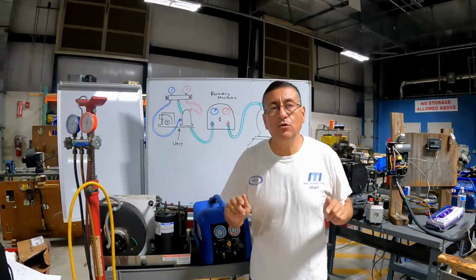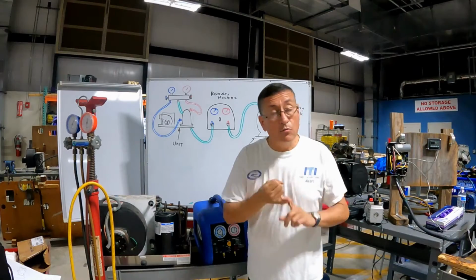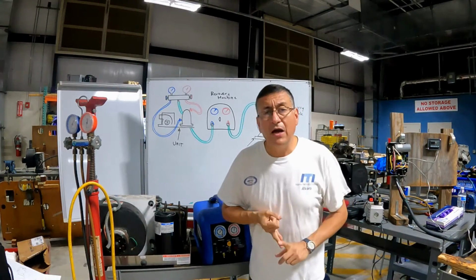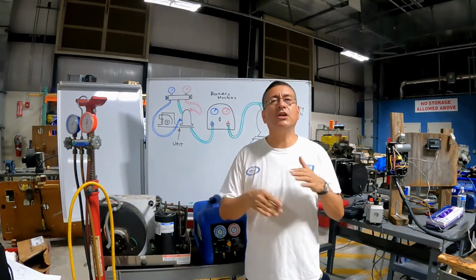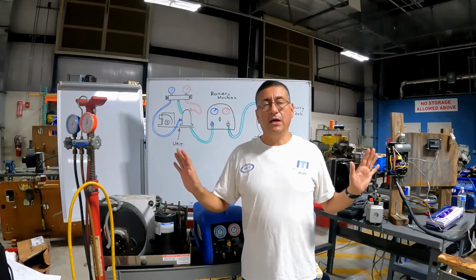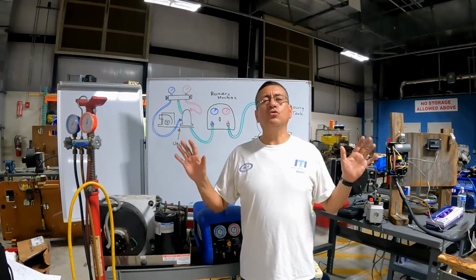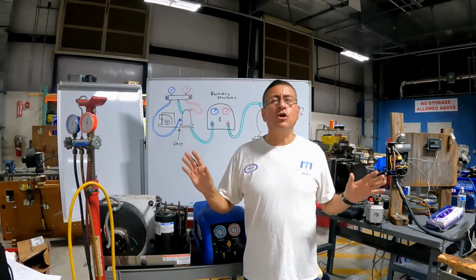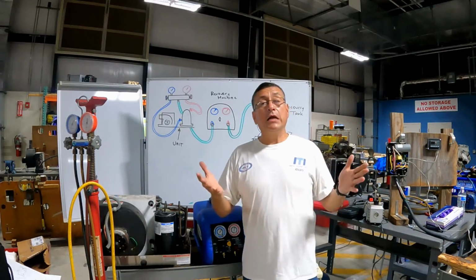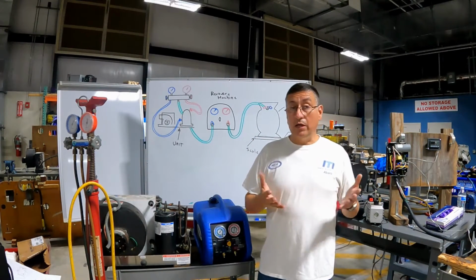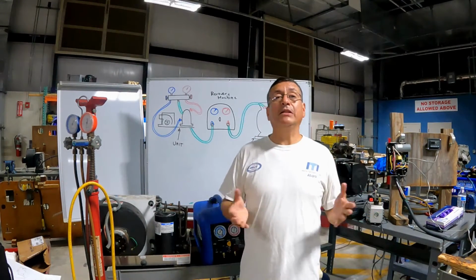In other words, in marine applications, the push-pull method is not recommended, because the majority of our equipment has accumulators, reversing valves, and heat pumps. This is not recommended in our business. Okay, we are going to use normally liquid or vapor. The most common is the vapor method. And right now we are going to check the procedure to do that method.